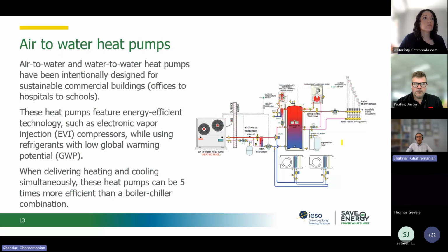One thing before I jump into the retrofit process, I want to bring your attention to air to water heat pumps. As I showed you before, water is better than air. If there is a possibility, or if our buildings have a hydronic system, then air to water or water to water heat pumps are good for sustainable commercial buildings like offices, hospitals, schools, and so on. They use different technologies. They use an electronic vapor injection compressor, and they have refrigerants with a low global warming potential, and their efficiency can be up to 5 times better than the conventional boiler and chiller.